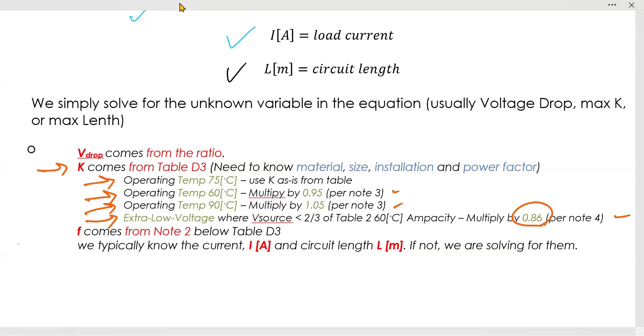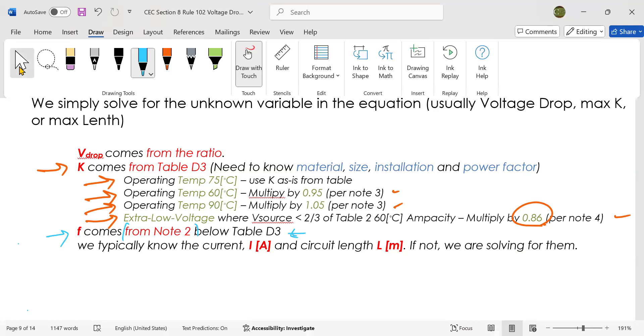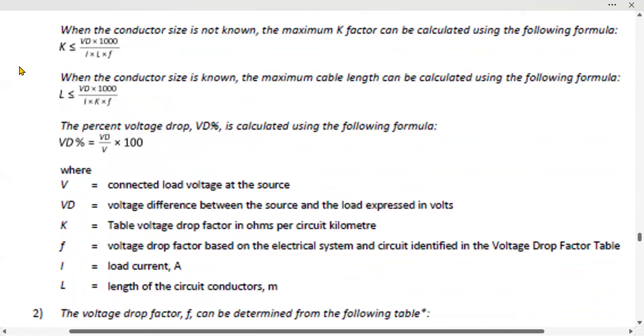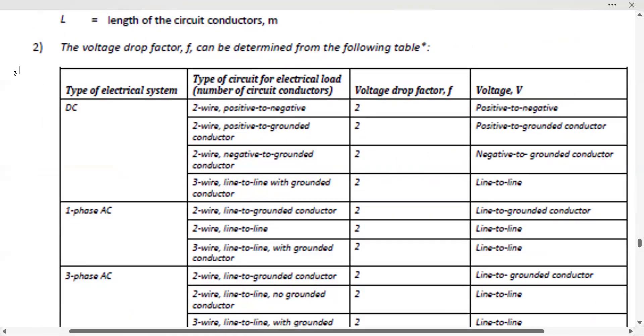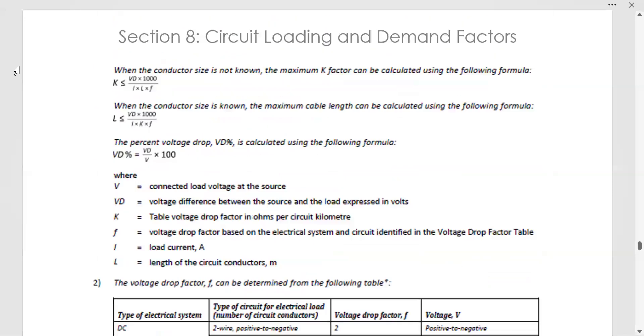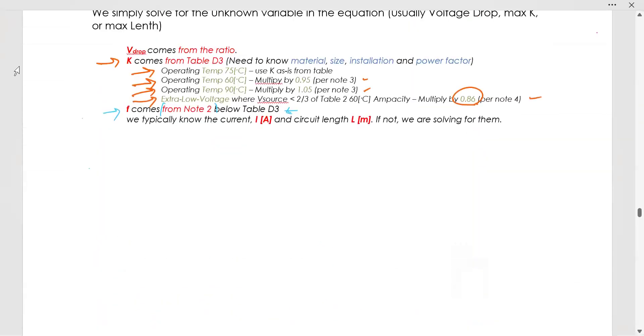Now moving on, the other variable is F. And the variable F comes from note 2 below table D3. So the factor F has its own table inside a note. Note 2 is the voltage drop factor F. It's going to be either 2 or 1.73. And that's it.